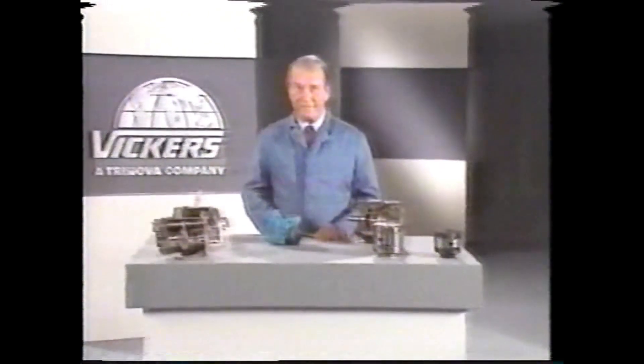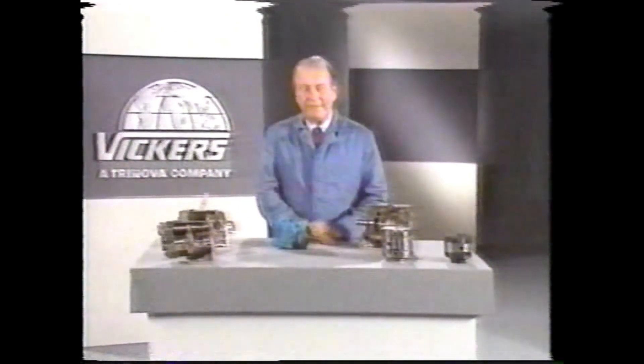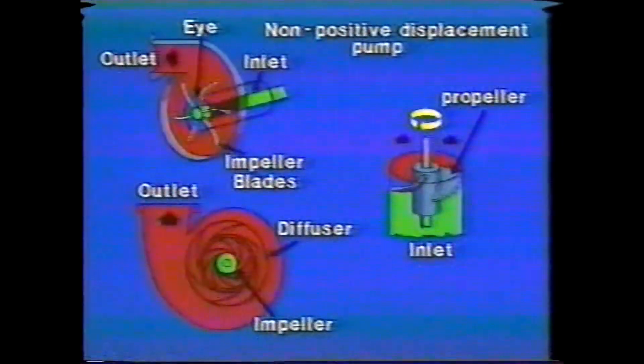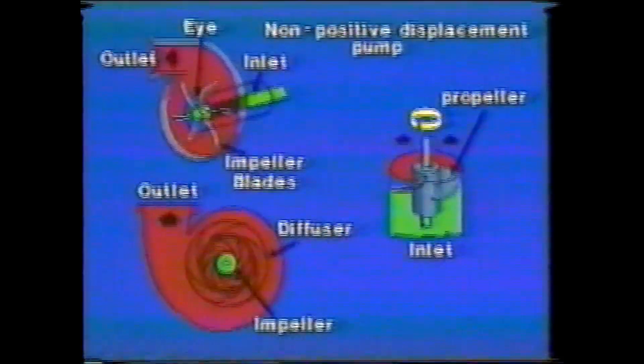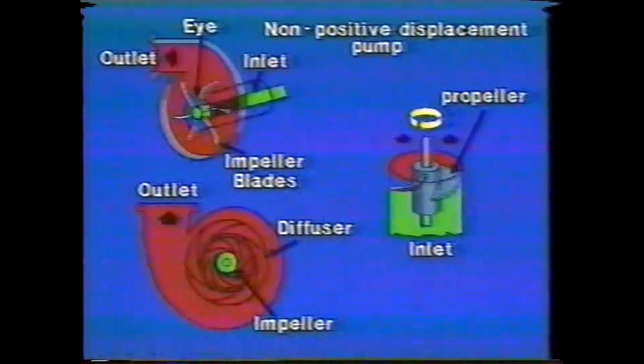Pumps fall into two basic categories: positive displacement and non-positive. Non-positive pumps are used primarily for circulating or transferring fluids. Examples would be the water pump on an automobile engine or one used in a dishwasher or washing machine. Most non-positive pumps operate by centrifugal force. Fluids entering the center of the pump housing are thrown to the outside by means of a rapidly driven impeller. There is no positive seal between the inlet and the outlet ports, so the pressure obtained is a function of the drive speed. The output flow decreases as the resistance increases.